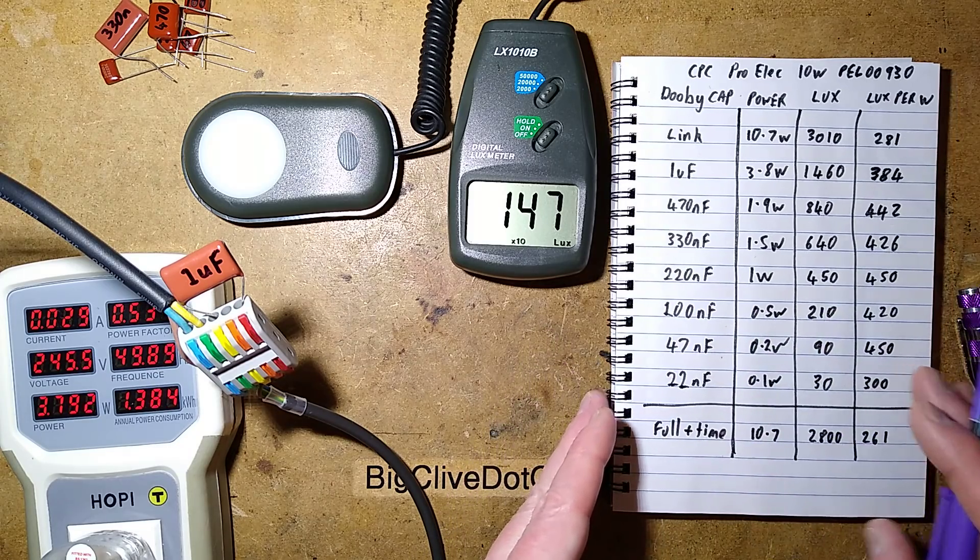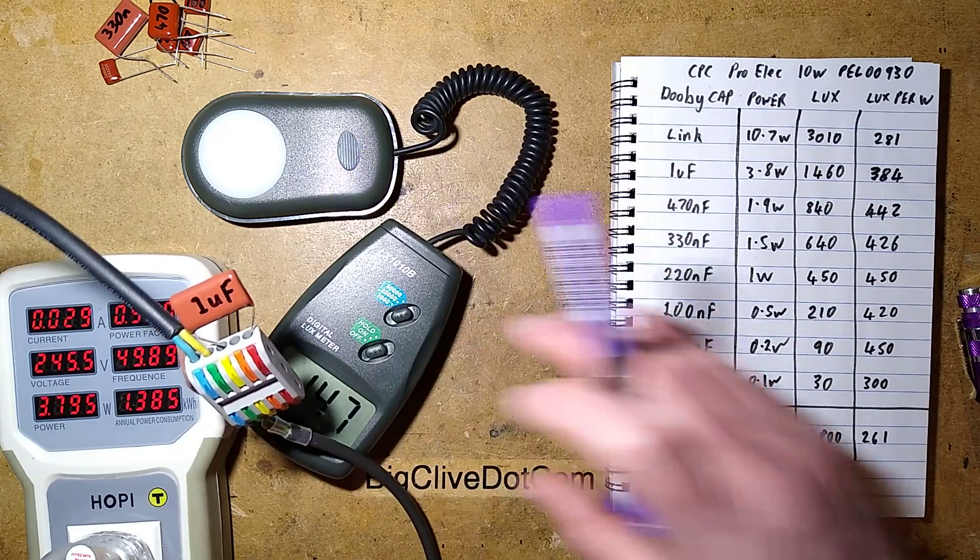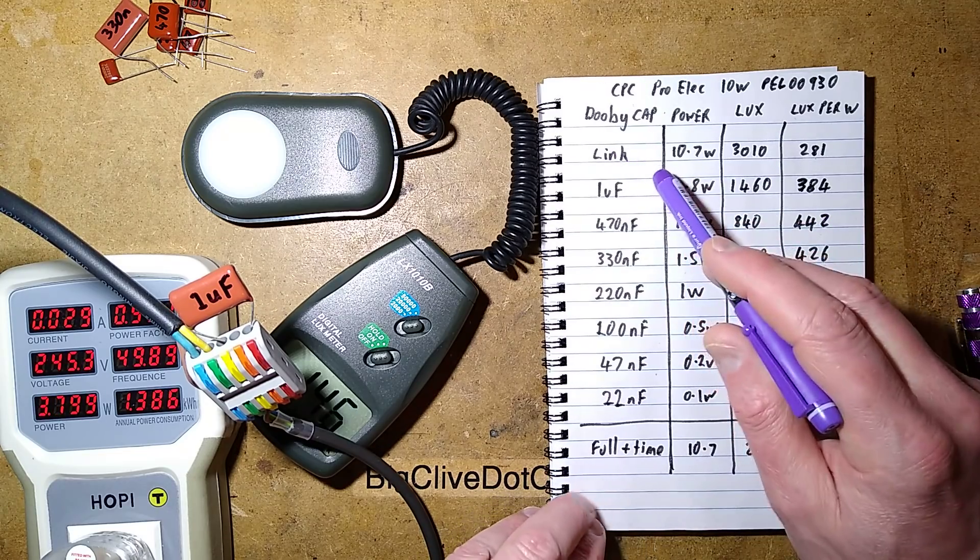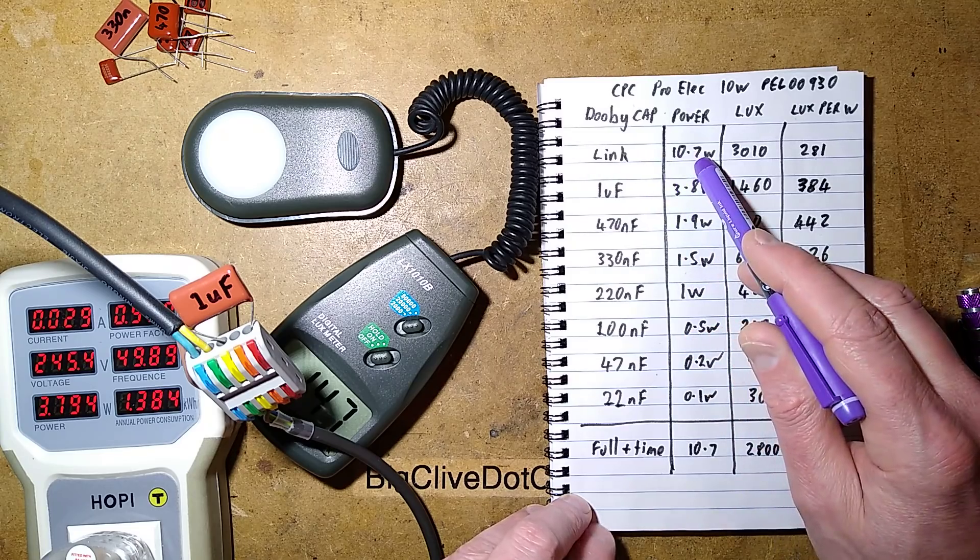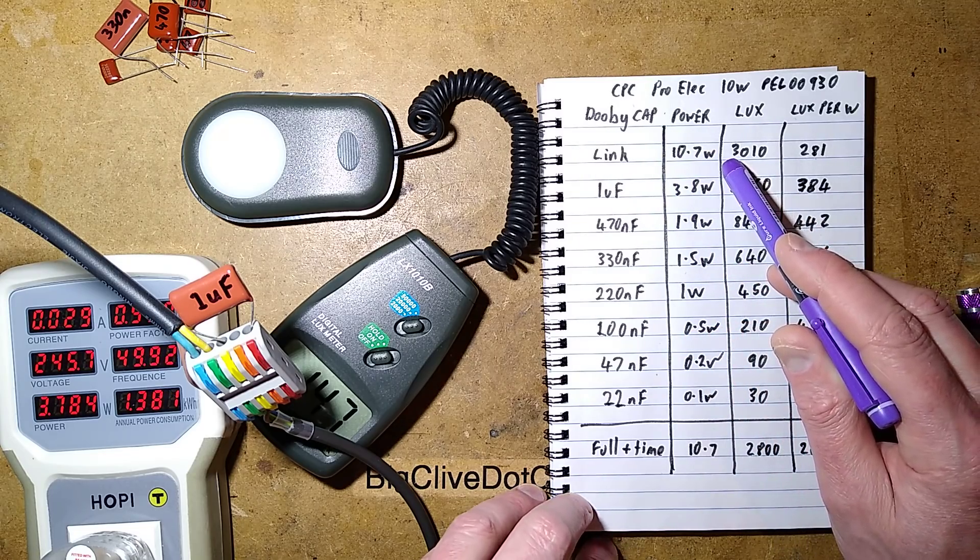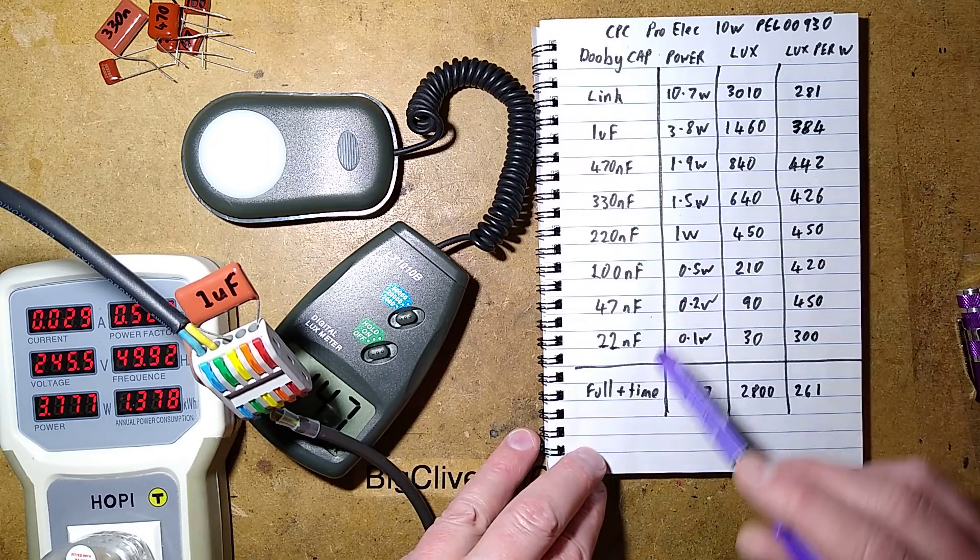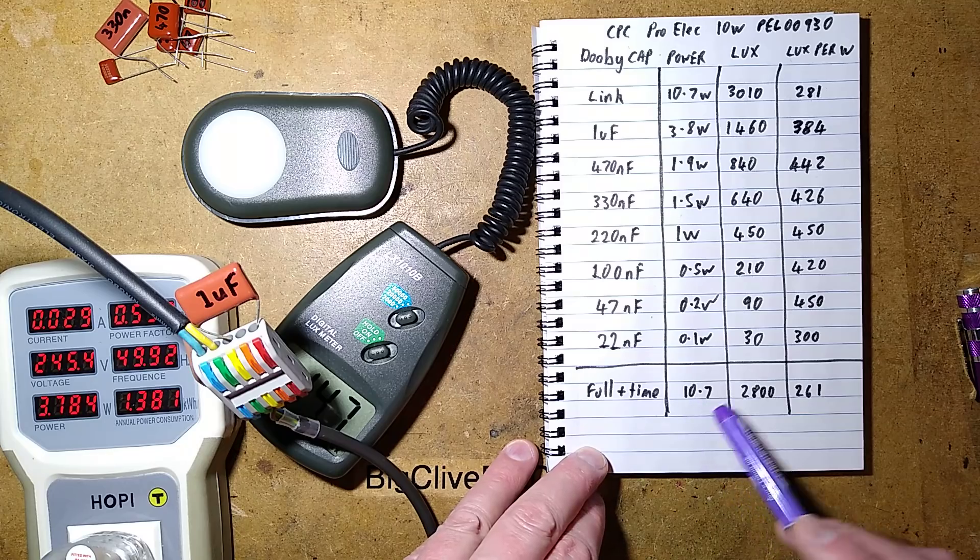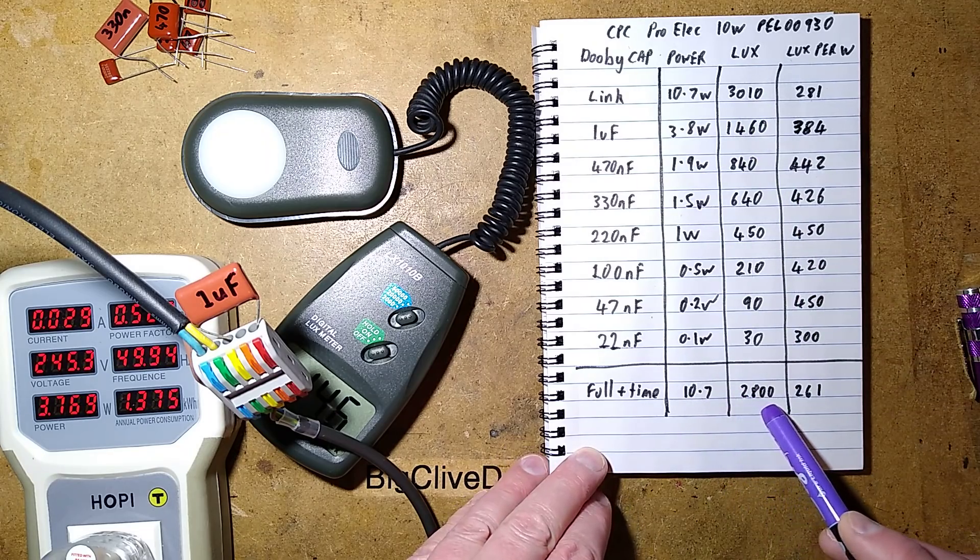When I did the test, I decided initially, I just powered it up briefly with the wire link in at 10.7 watts and it was showing 3,010 lux. I decided afterwards just to leave it running for a while, so I went for a bite to eat and once it had heated up, the 3,010 lux, it was drawing the same power, dropped to 2,800 lux.